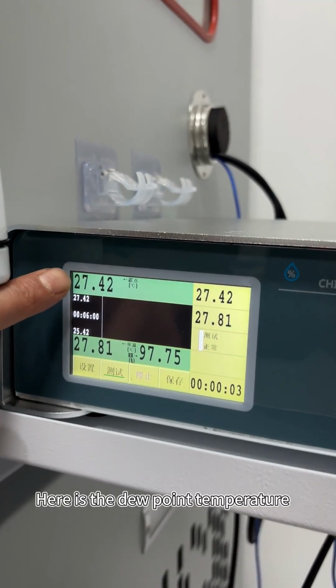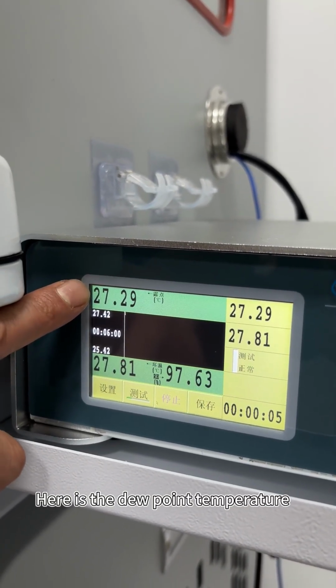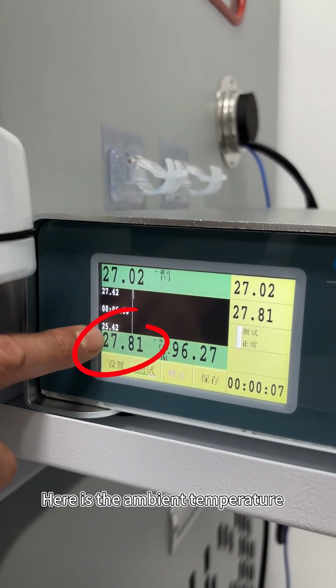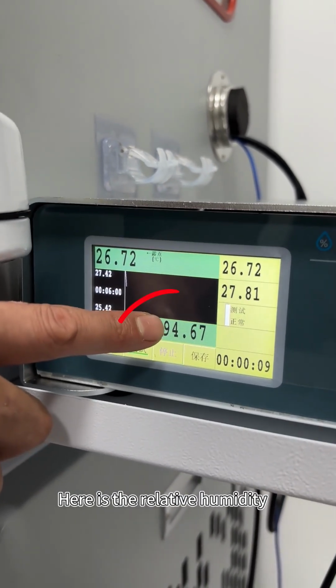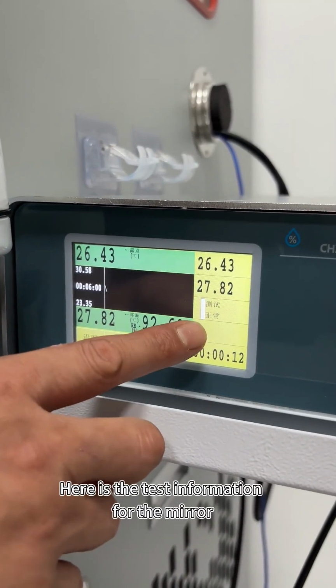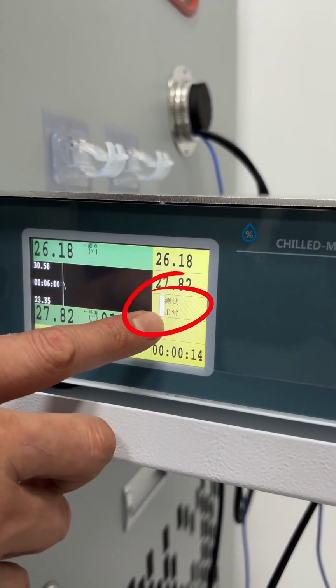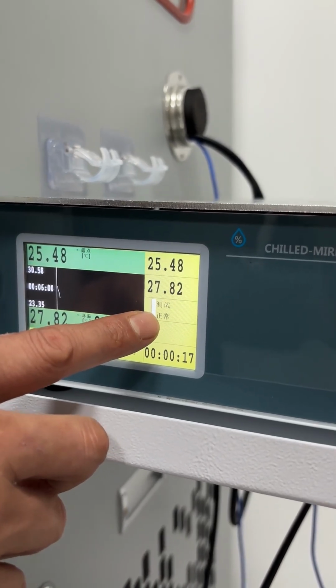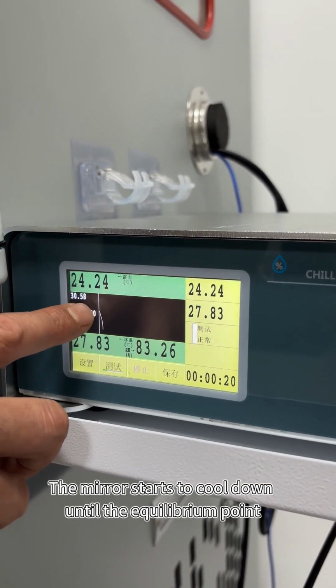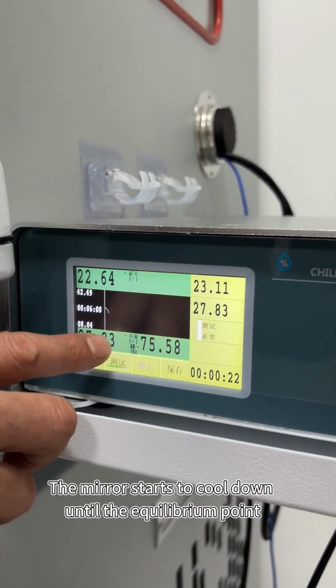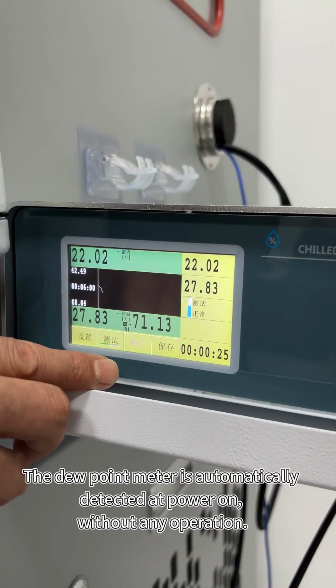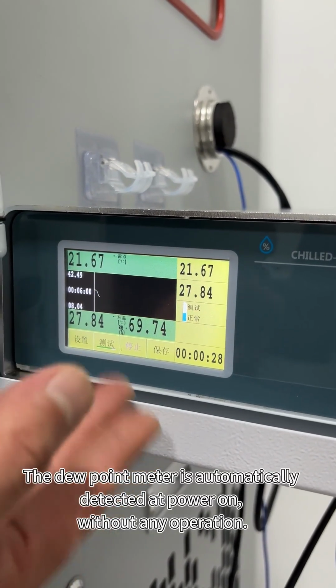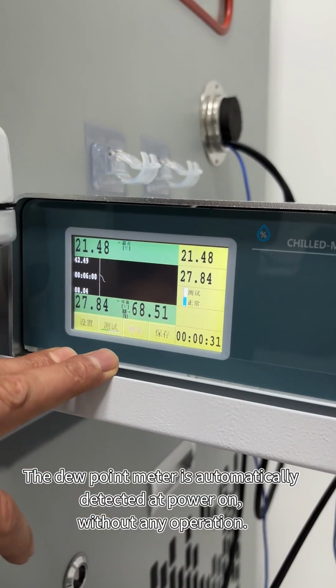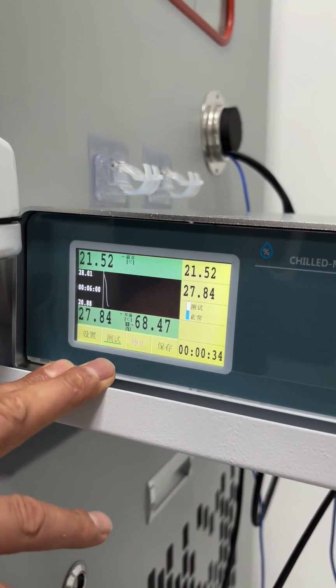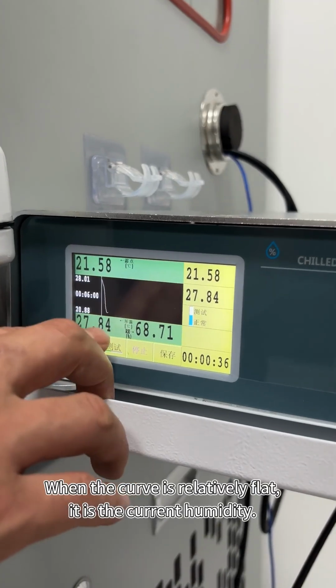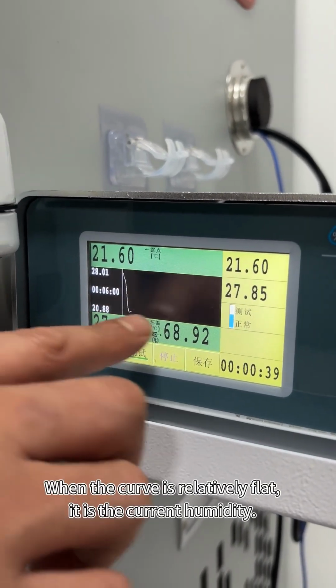Here is the dew point temperature. Here is the ambient temperature. Here is the relative humidity. Here is the test information for the mirror. The mirror starts to cool down until the equilibrium point. The dew point meter is automatically detected at power on without any operation. When the curve is relatively flat, it is the current humidity.